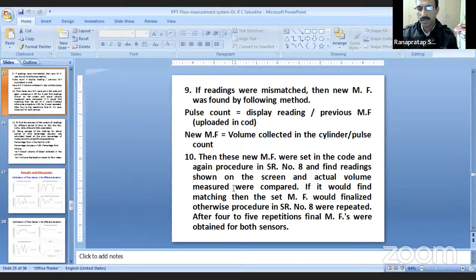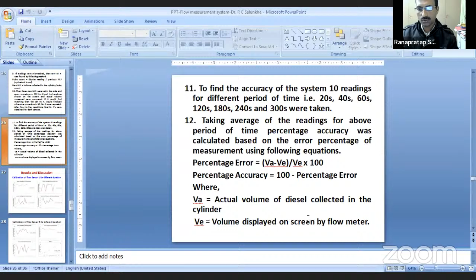So again, we use this formula: pulse count is equal to display reading divided by the previous multiplication factor, and then we find the new multiplication factor. This new multiplication factor is again inserted into the code, and this code is uploaded into the system. After doing this 4 to 5 times, we get the exact multiplication factor, and our readings are close to what is actually collected in the cylinder. With this, we do the calibration.